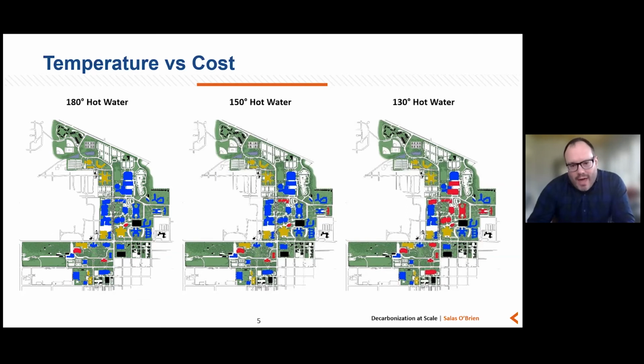And we let that drive the technology selection, the ground source heat pump plan, and the distribution system and piping to figure out how to balance cost versus effectiveness. We'll talk about other campuses and the efficiency gains, or potential gains, that are left on the table if you make different selections. But Ball State was designed for 150 degree hot water. It actually operates these days at about 140 degrees as a hot water supply temperature.